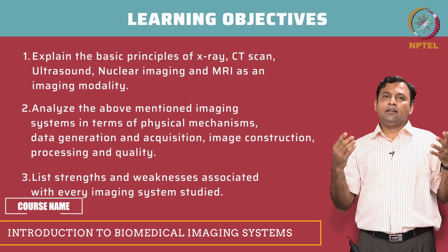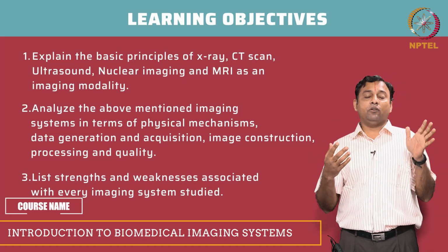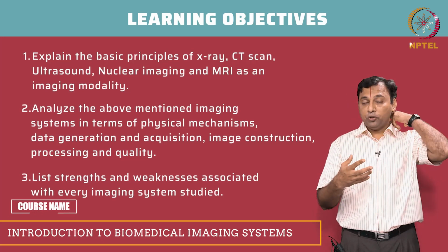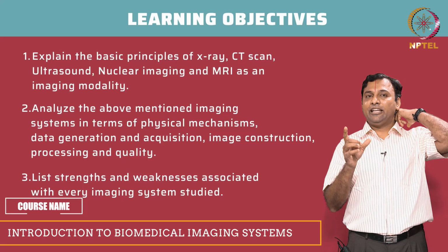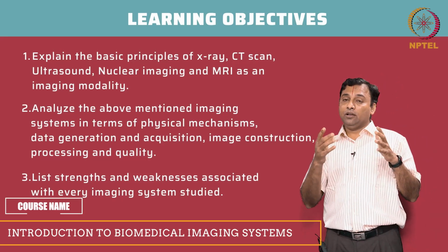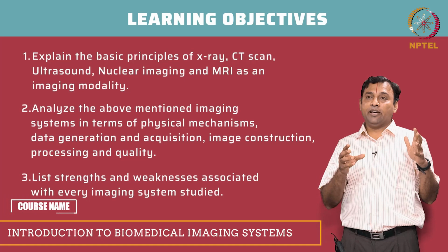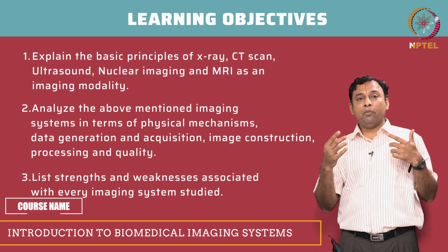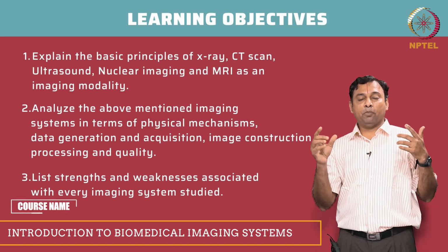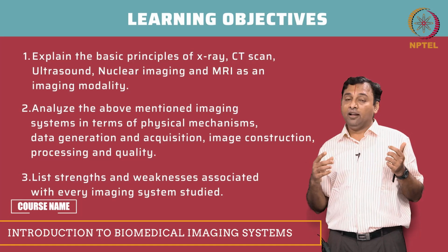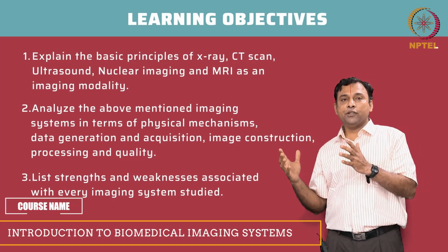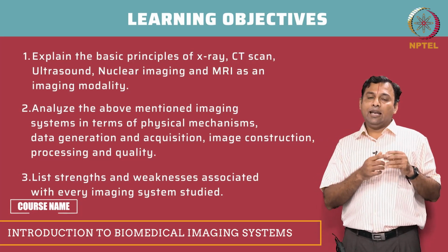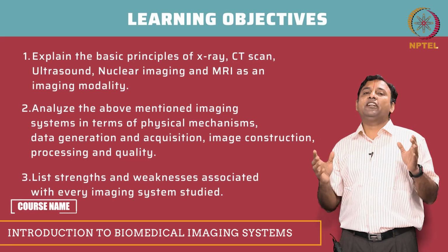When you say analyze, if there is an image, there is a problem, the doctor will say, okay, look, this is abnormal or normal, I have to diagnose. Is there a problem with the system? So you should be able to analyze the image, not the imaging system. That means look at it and say, look, this is probably an artifact from the system. Or there is a sensor that is broken, maybe an artifact from image reconstruction, or maybe the computer, we had a new patch and therefore the precision changed and therefore this is an artifact from that. So you should be able to analyze from the end user's complaint as to what could be the possible place you want to focus.